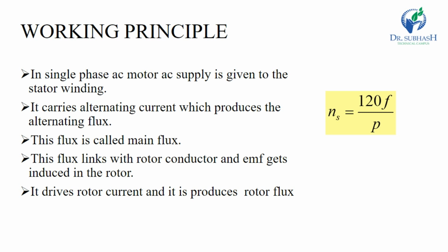The rotor never catches up with the stator field due to the friction and inertia of the rotor, and the induction motor always runs at a speed slightly less than the synchronous speed, and the difference between the two speeds is termed the slip speed. The direction of rotation of the induction motor can be changed by changing the phase sequence of the supply.